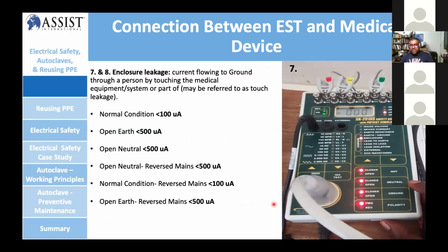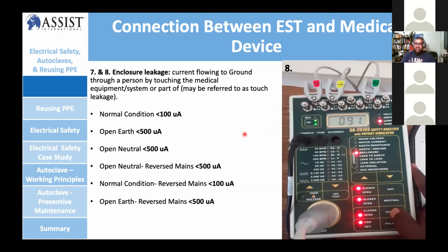So on enclosure leakage, you have to do steps like 1, 2, 3: normal condition, open earth, open neutral and reverse condition, and then normal condition, reverse mains, open earth, reverse mains. So you have almost 6 steps to comply with. These are things that you do, single fault and normal condition, to verify whether there is any leakage coming out in any of these particular conditions. If the leakage is above the particular range, that means something is wrong with your device that you need to look into.